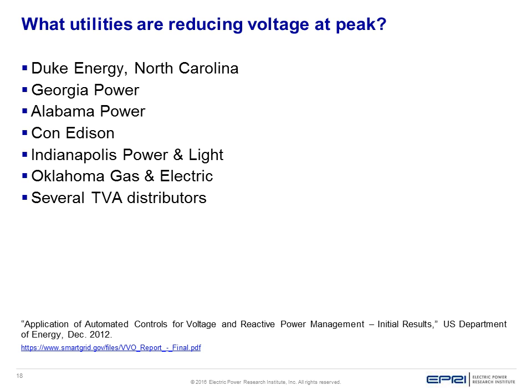So you end up with, for example, maybe having to have high voltages near the substation to supply a customer at the end with acceptable voltage, because as you go out from the substation on a circuit, the voltage tends to drop. So being able to reduce voltage at peak can actually be trickier than doing it under lighter load conditions.